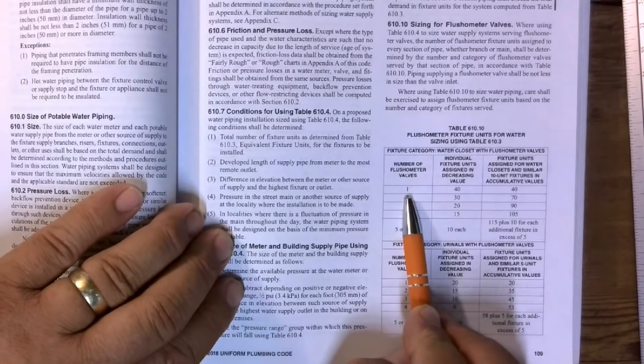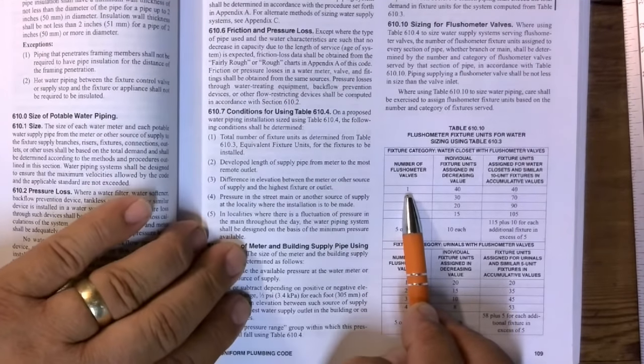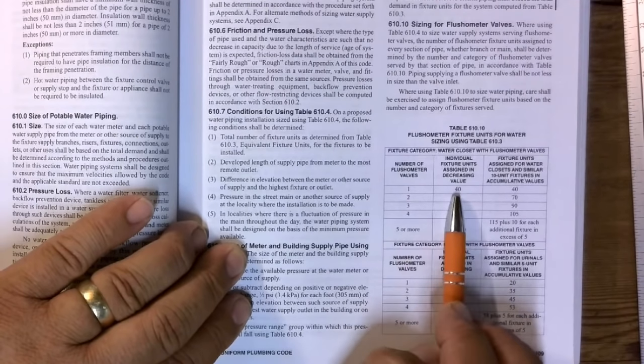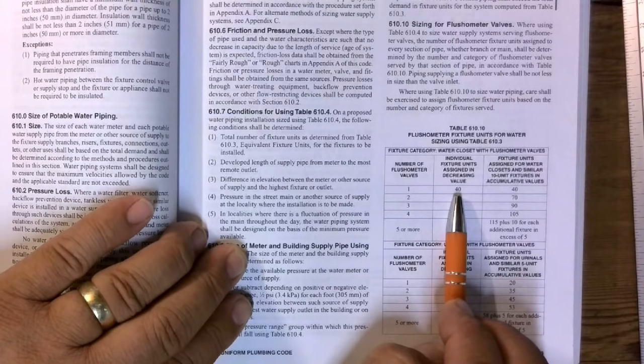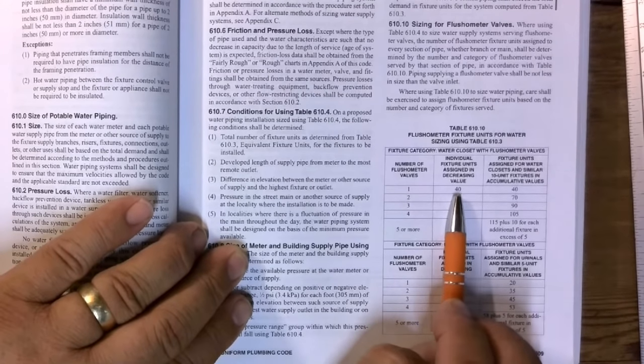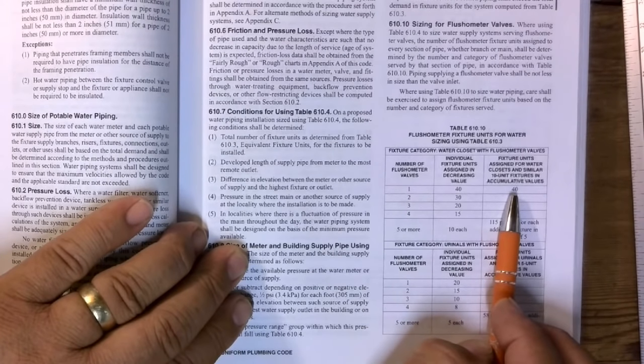So if I have one flushometer valve, one piece of pipe, and the only thing on it is one flush valve, your fixture unit value for that flushometer is 40 fixture units. In other words, it's like hooking up 40 lavatories. So the fixture units assigned for your water closets and similar fixtures is 40.